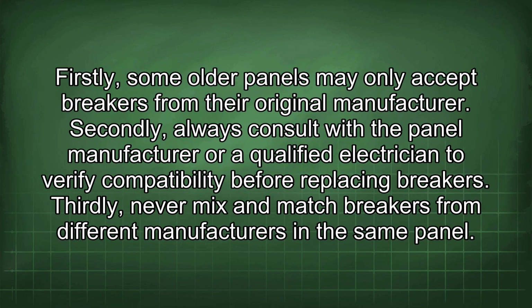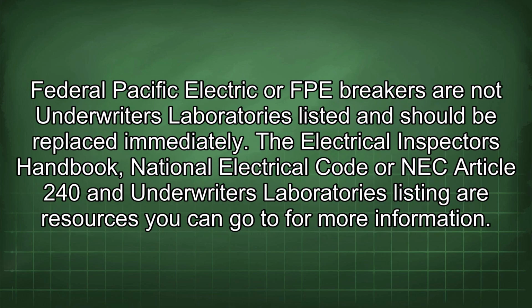Firstly, some older panels may only accept breakers from their original manufacturer. Secondly, always consult with the panel manufacturer or a qualified electrician to verify compatibility before replacing breakers. Thirdly, never mix and match breakers from different manufacturers in the same panel. Federal Pacific Electric or FPE breakers are not Underwriters Laboratories listed and should be replaced immediately. The Electrical Inspector's Handbook, National Electrical Code or NEC Article 240 and Underwriters Laboratories listing are resources you can go to for more information.